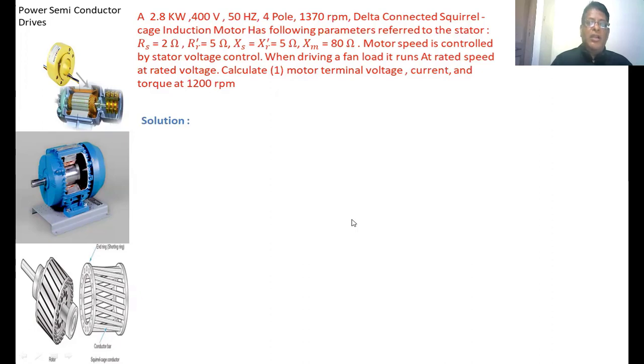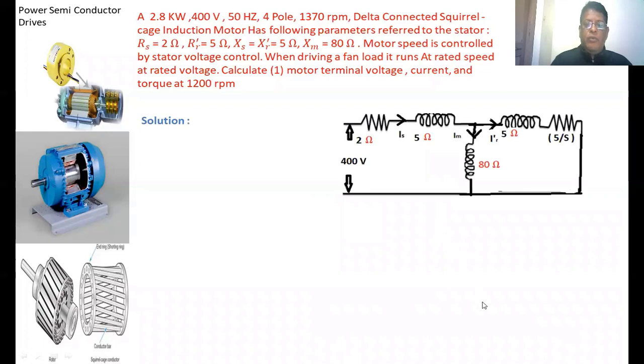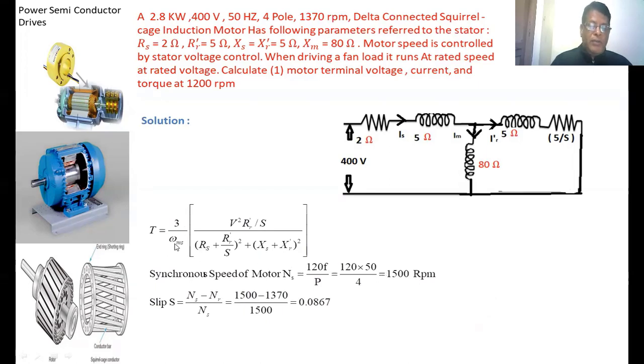Calculate the motor terminal voltage, current, and torque at 1200 RPM. We are using the equivalent circuit of the induction motor where the core loss resistance is neglected. The slip of the induction motor S = (synchronous speed - actual speed) / synchronous speed = (1500 - 1370) / 1500. Here 1370 RPM is the full load speed given in the problem, so this slip corresponds to the full load speed.